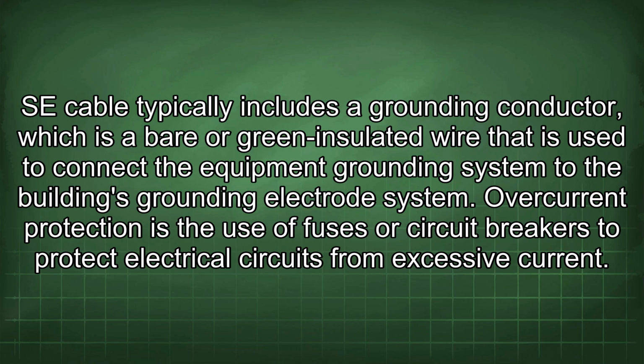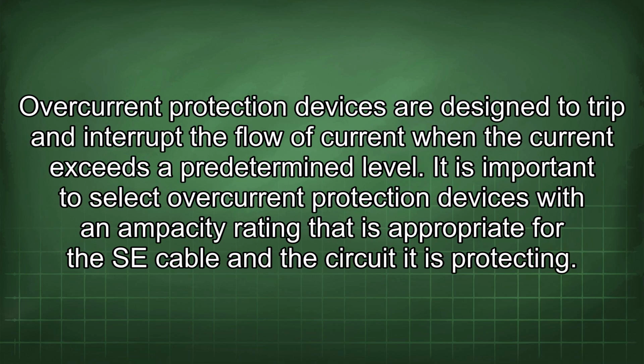Overcurrent protection is the use of fuses or circuit breakers to protect electrical circuits from excessive current. Overcurrent protection devices are designed to trip and interrupt the flow of current when the current exceeds a predetermined level. It is important to select overcurrent protection devices with an ampacity rating that is appropriate for the SE cable and the circuit it is protecting.